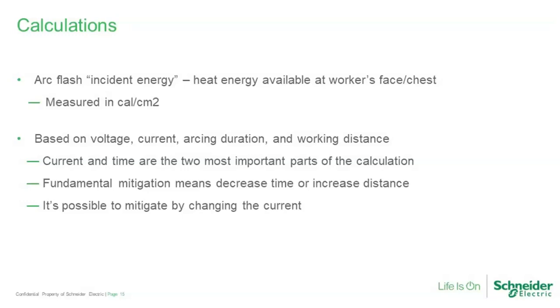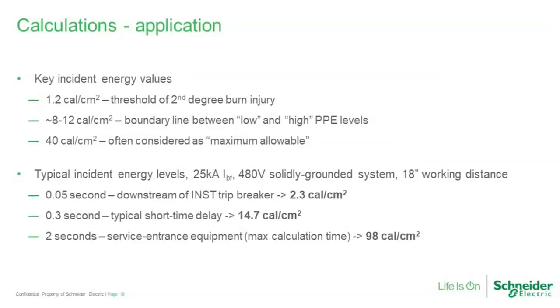We may go from the instantaneous region of a breaker to the short time region, for example. So you have to be careful when you're looking at these mitigation means. Sometimes you change one thing and affect other things in ways that you don't necessarily anticipate. And so we have to be careful when we start figuring out how we're going to deal with the problems.